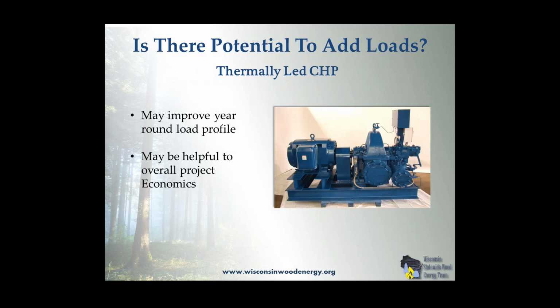Again, as part of the potential project trying to address additional loads, there is the opportunity, if the load is of appropriate size and capacity across the year, to add thermally led combined heat and power, and that'll add load during different parts of the year, and it also will have a positive impact in most cases on project economics. In most cases, with thermally led CHP, we're talking about electricity costs for that generated from the CHP unit in the 2 to 3 cent per kilowatt hour range versus utility costs, electric costs that may range from 6 cents a kilowatt hour to 18 to 20 cents per kilowatt hour, depending on what part of the country you're in.